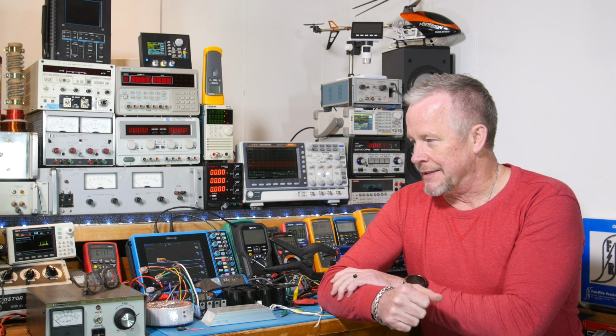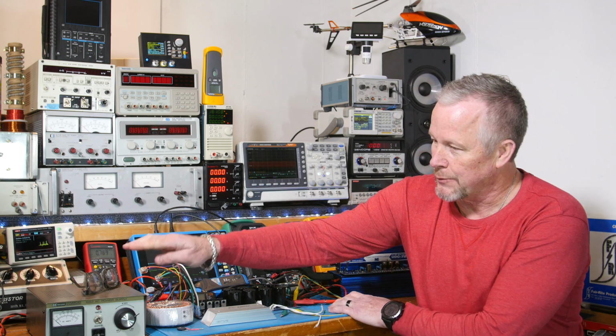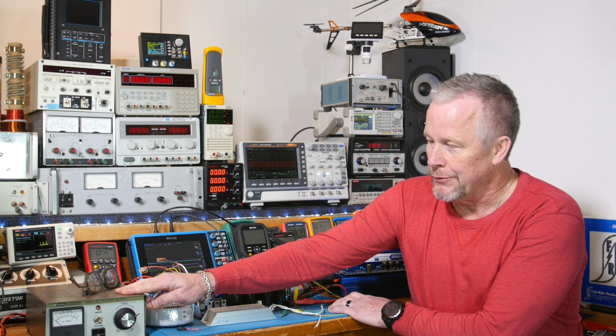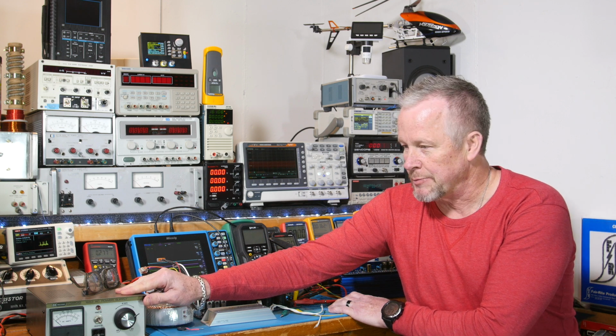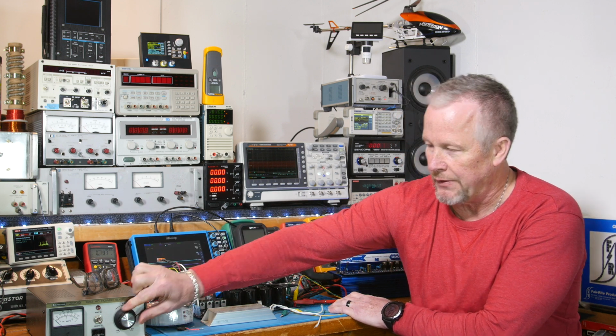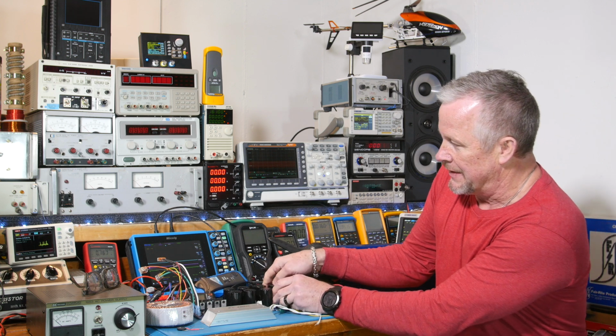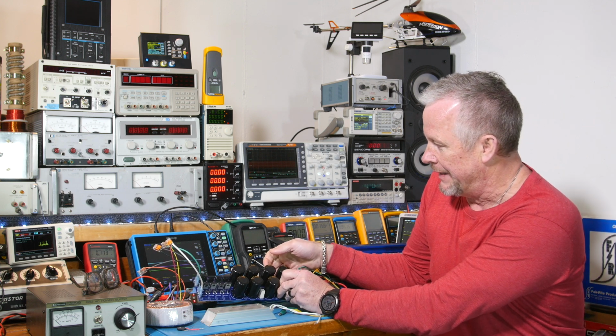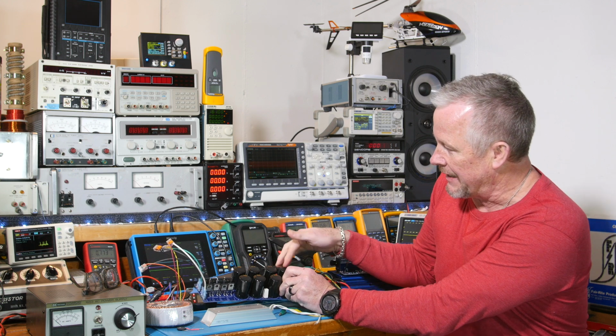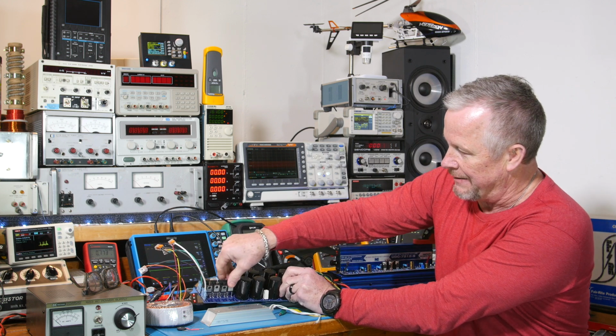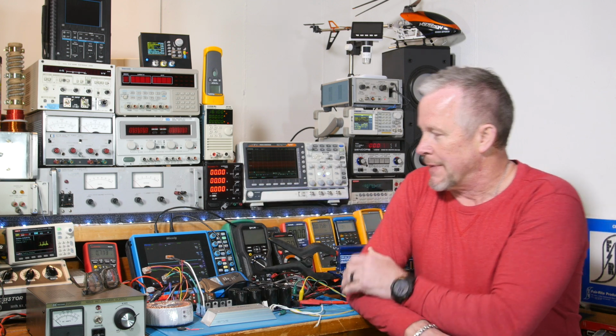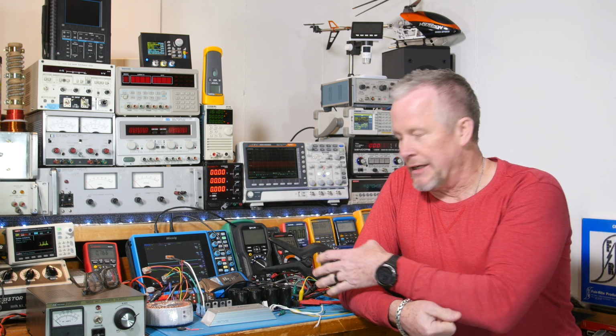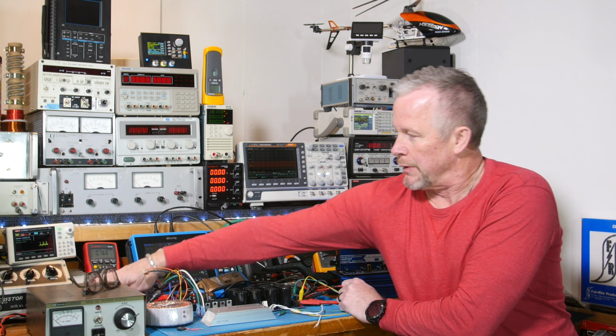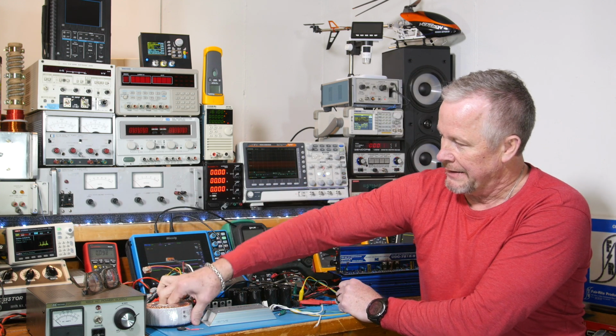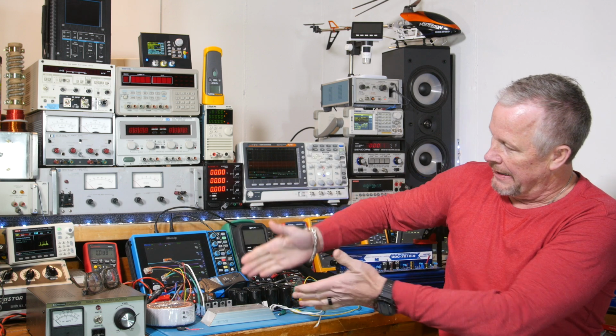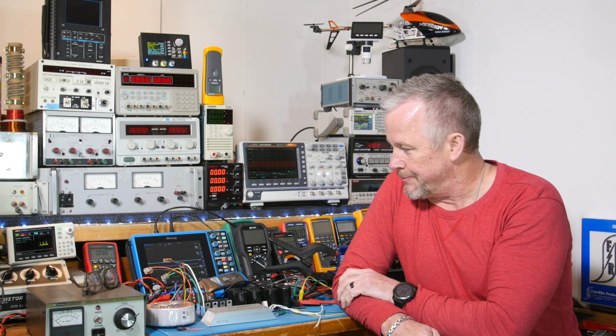So for instance, the first way we're going to test this is we're going to hook this up into this B&K Precision Power Supply. It's got an isolation transformer, this Variac, and we're going to power up this Jean Hiraga Power Supply, the Le Monster, which has 80,000 microfarads of capacitance and big old bridge rectifiers. We're going to power this up and watch the inrush current when we hit that power switch.